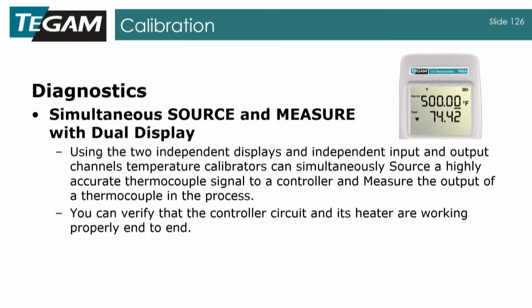One of the useful things about a calibrator is simultaneous source and measure: on the display you can source the temperature but also watch a temperature input. That's useful in a number of ways when monitoring a process. You could put your calibrator in the loop and see what signal is coming in, then feed that out of the output. Or you could simply use this as a reference thermometer, simulating a temperature while watching with your control system how it responds with another input sensor.